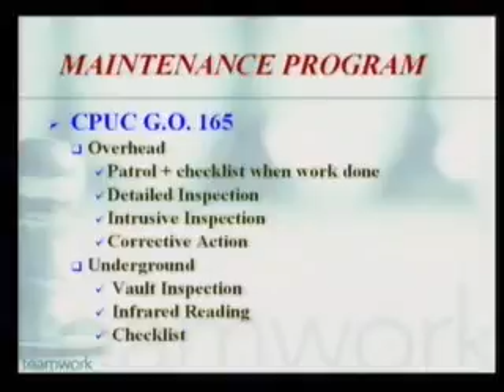And for the underground, the main component of our underground system is really our vaults. We have a lot of system through vaults, and we have a procedure in place that every time we go in to a vault, we have a checklist. We do infrared testing. We check for conditions of every equipment that's in that vault, and again, that's recorded, and we have a database that we use to track that.